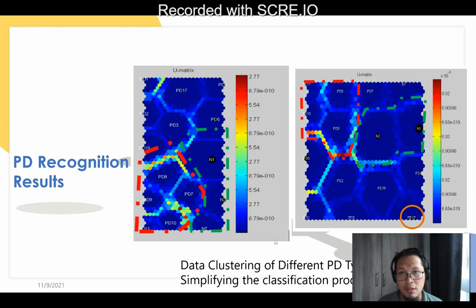Next, for the PD recognition result, you can see that for these simulations I compared a few inputs that mix the normal signal and the PD signal. You can see that the severity is clustered compared to the normal one. So this is the most important thing, because we don't want to put our decisions at risk, especially for a transformer that has a normal signal compared to PD signal activity.